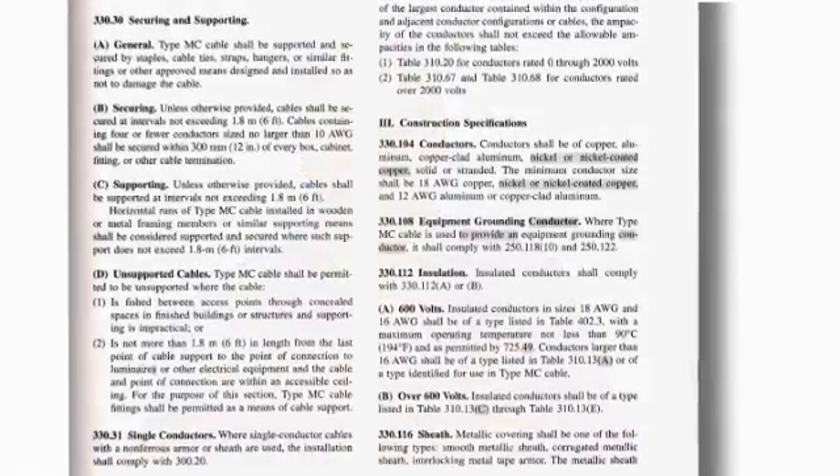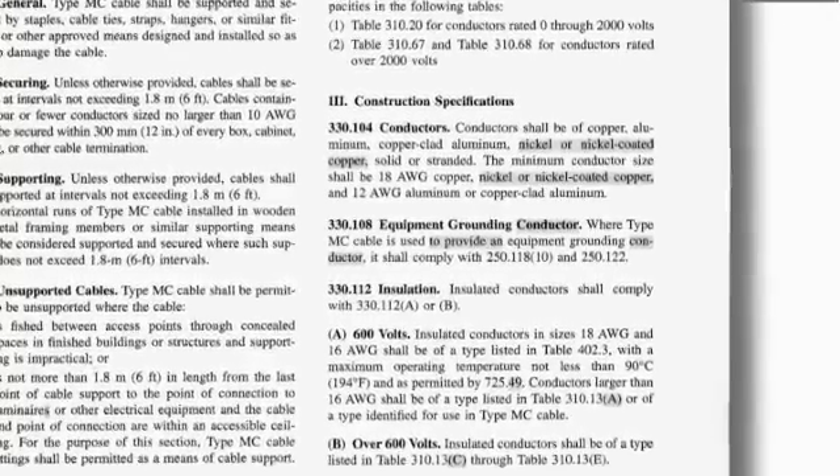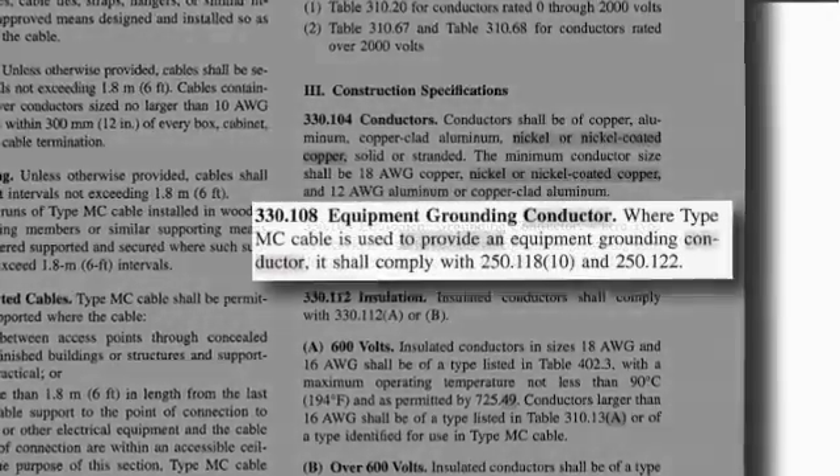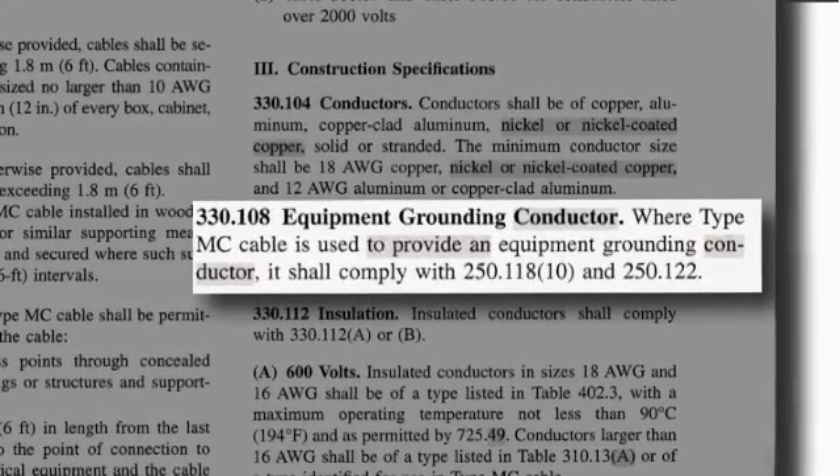The NEC does permit the armor of MC cable to serve as the ground path for the cable. NEC Section 330.108, covering equipment grounding for MC cable, requires that where MC cable is used for equipment grounding, it must comply with 250.118(10) and 250.122.